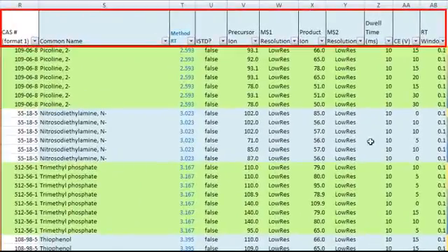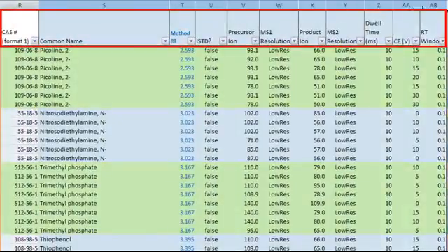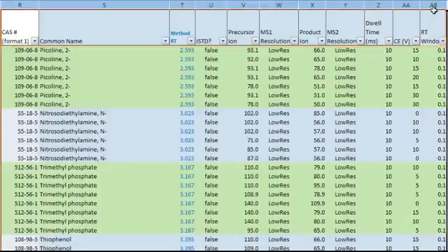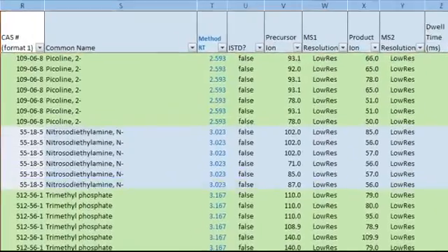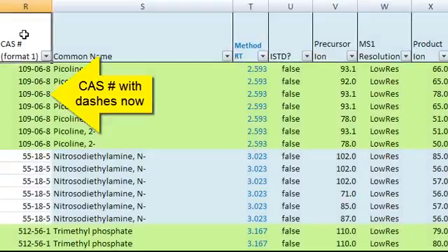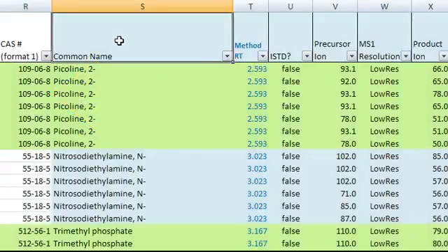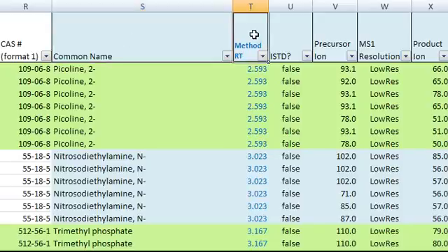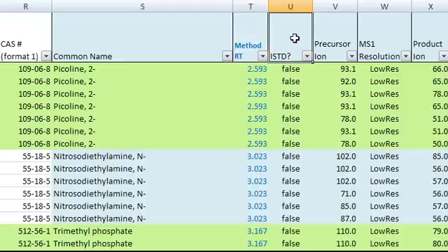These highlighted columns have all the information needed to build a MassHunter MRM acquisition method. CAS numbers have dashes now. Common name again. Due to the MassHunter requirements, no special characters or Greek letters are allowed in this common name column. This column is the retention times of the method that you are going to use. Is this compound an internal standard, true or false?